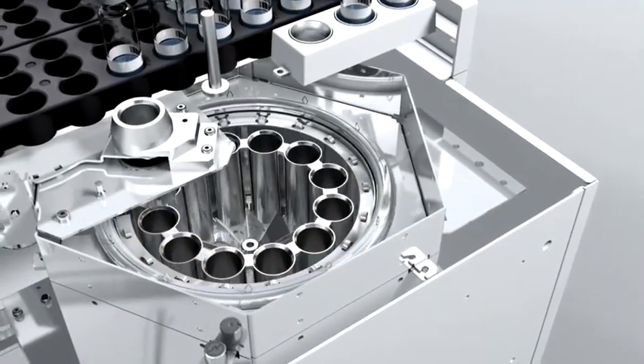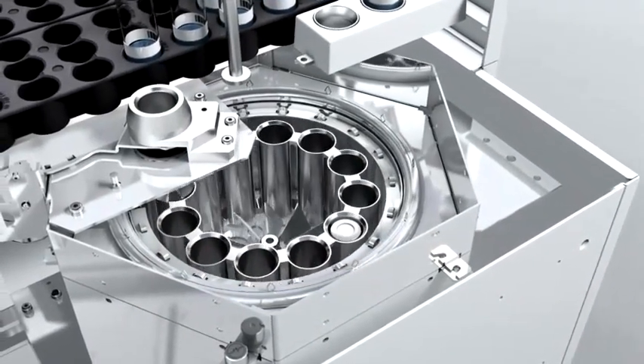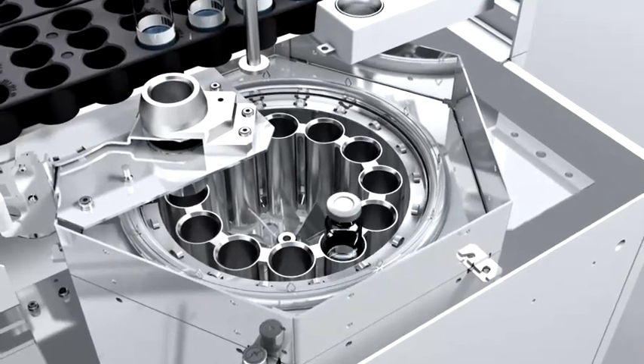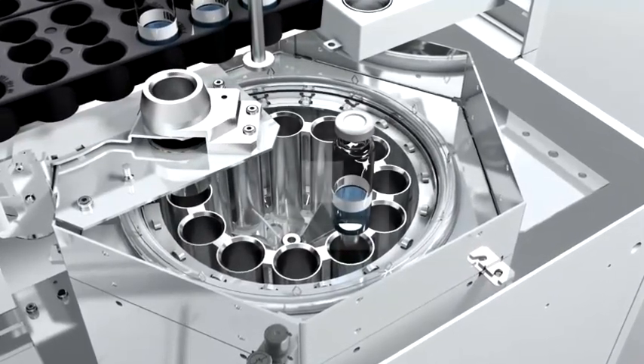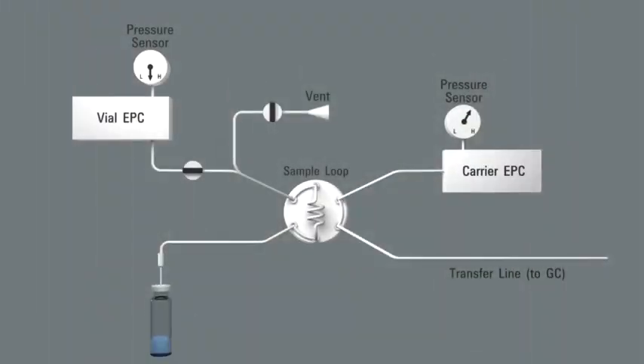Automated Intelligent Scheduling takes care that each vial is taken at the right time from the oven to the sampler. The vial's septa is pierced by the sample probe, and then the vial is minimally pressurized with inert gas. The sample loop is then filled with the Headspace gas from the vial.